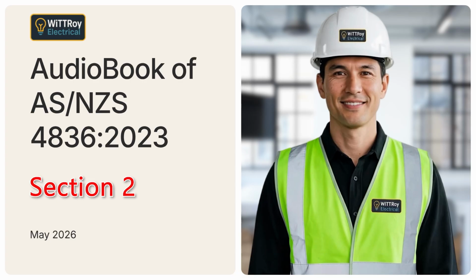This is one of the strongest safety messages in ASNZS 4836. Do not assume a conductor is safe because it is neutral. Do not assume an earth conductor is safe because it is connected to earth. Do not assume equipment is safe because a switch is off. Prove it before touching. This clause also reminds us that non-electrical energy sources may need to be isolated, controlled, or secured. For example, machinery may have counterweights, hydraulic pressure, pneumatic pressure, springs, stored movement, or other stored energy. Electrical safety often needs to include these non-electrical hazards as well.